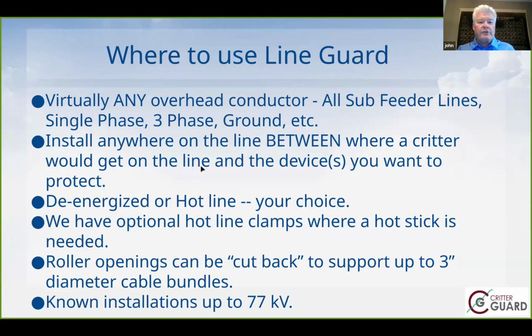So the point being, you can install line guard anywhere on the line between where a critter wants to get and the device. If the critter comes on at a tree, a building, or another pole, and you've got transformers or other powered devices down the line, it doesn't have to be right next to it.